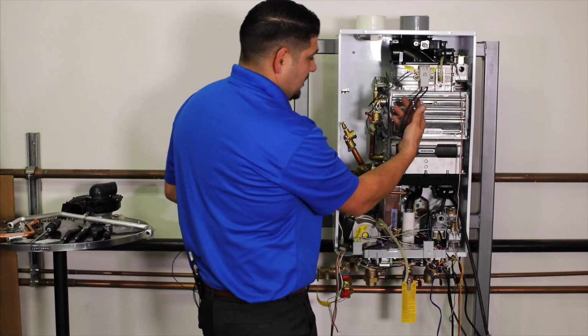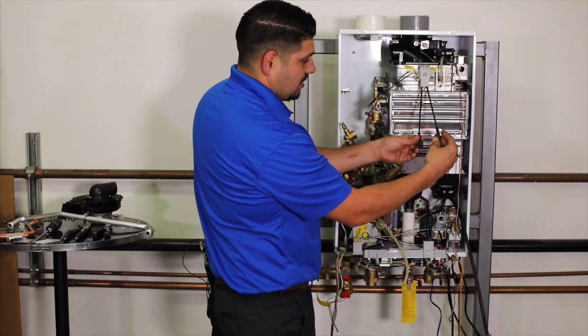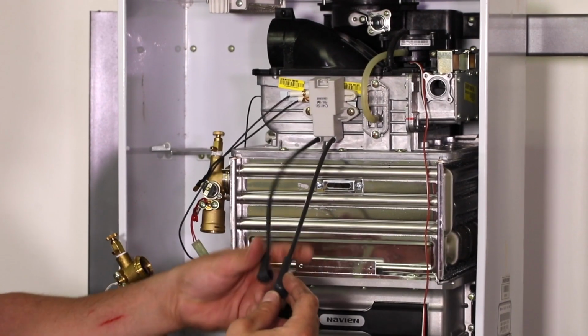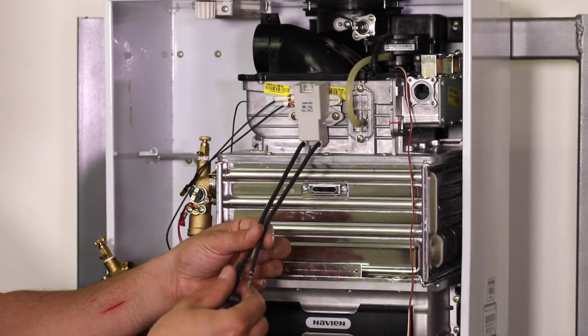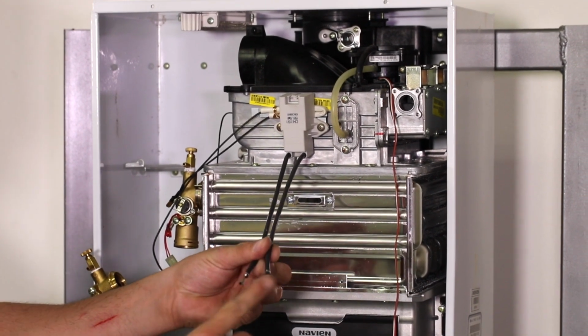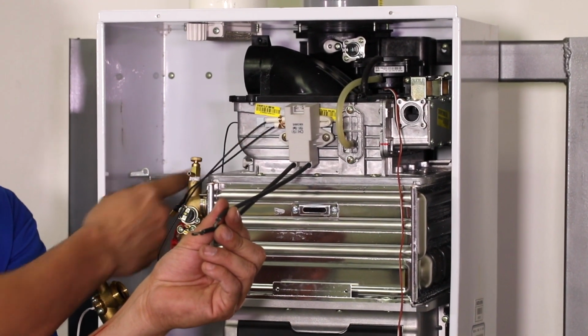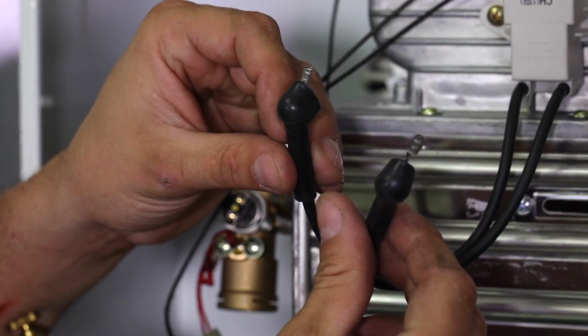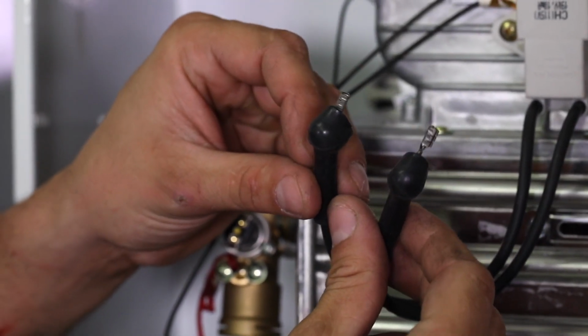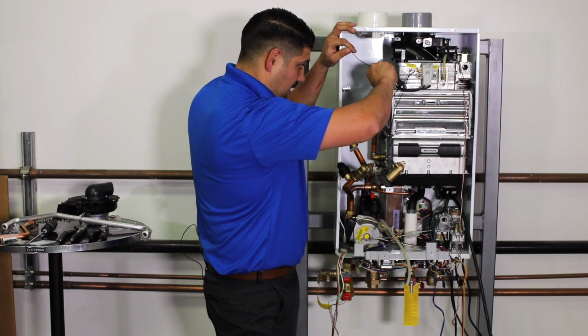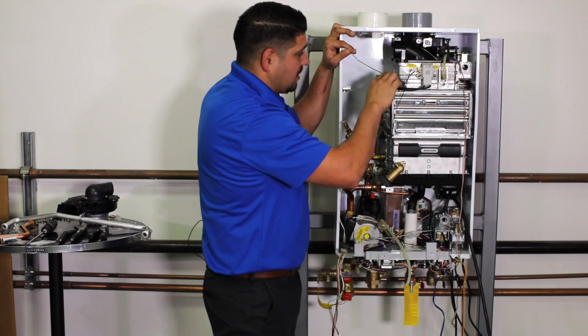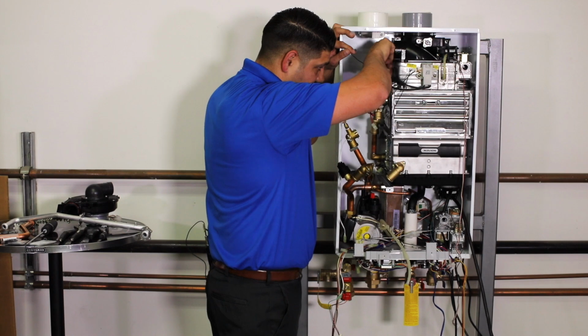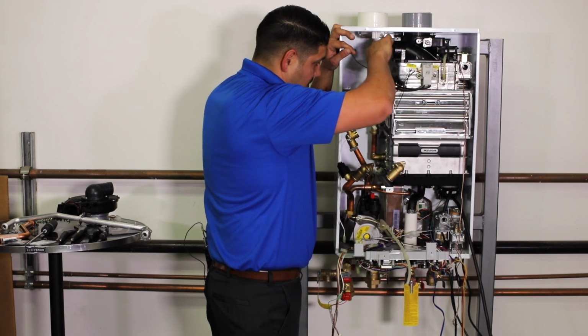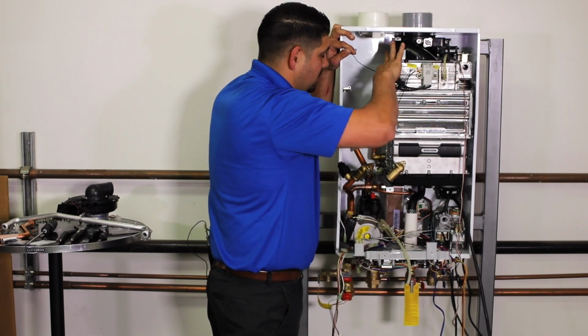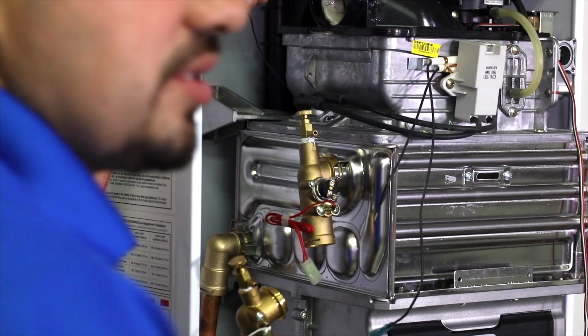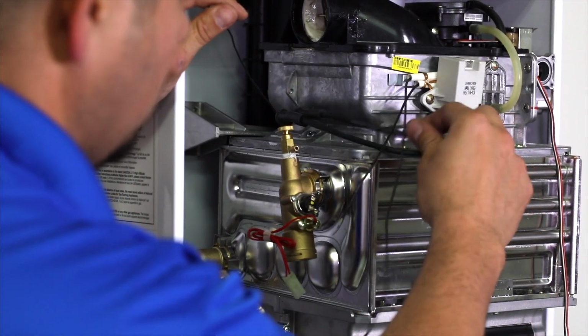Now, your ignition transformer has 2 leads going on, about the same distance. So you can slide the boot off, and you can see the terminal or the connector, which has got to go to these 2 sharpened points on your flame rod. These are going to create your spark. I tend to like to slide the boot back so I can ensure and visually see that it slid on properly. Now that I know they're both on, slide the boot back forward so it protects those and doesn't let any spark go. And now we've got a properly installed ignition transformer. Wires are pretty tight, they're not pulling off.